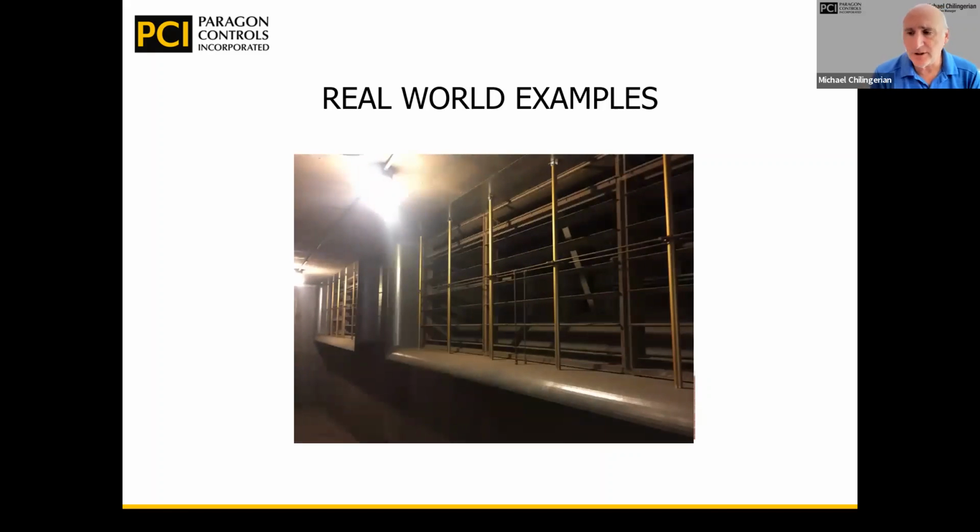Here's a job that I took a picture of at Sandia Labs, Albuquerque. It happens to be a very large indoor air handler. Just to the left of it was a supply air shaft, and you can even see there's a little dust on it. It's been in operation for a lot of years. I went over and took a look at it, and there are parts that are galvanized, parts that are anodized aluminum, and parts that are stainless. I found that the stainless and the anodized aluminum stayed the cleanest. The galvanized showed the most dirt. So it's a system that can work for a lot of years. Low maintenance, works very nicely. Bell mouth again.